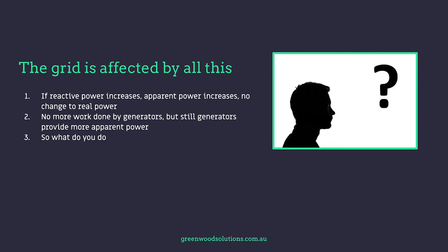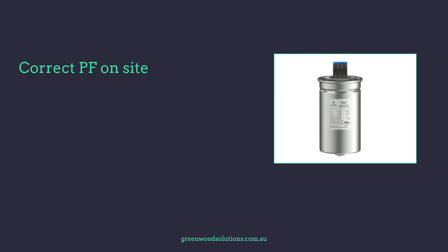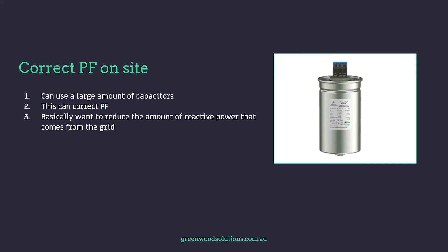So what do you do about this? One way is to correct the power factor on site. You can use a large amount of capacitors if it's a lagging power factor with inductive loads — this can correct the power factor. Basically, you want to reduce the amount of reactive power that comes from the grid, but you still need reactive power.